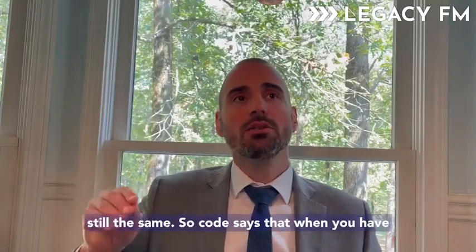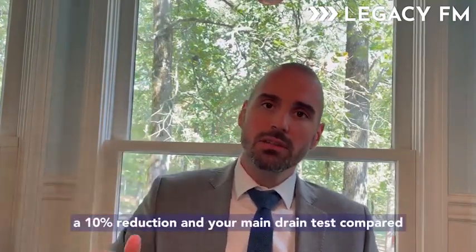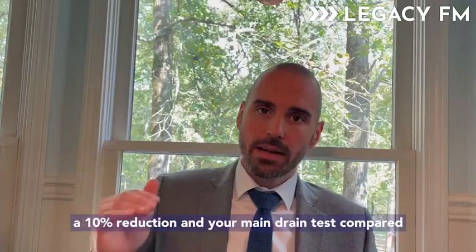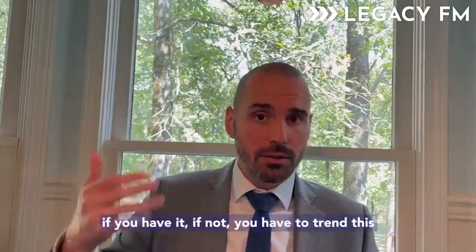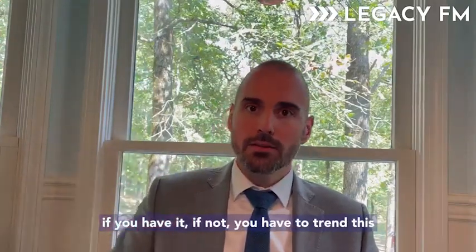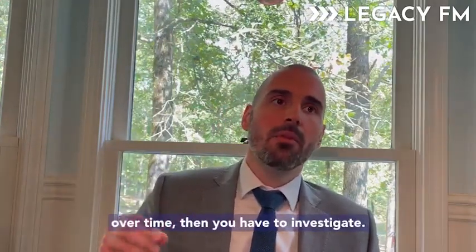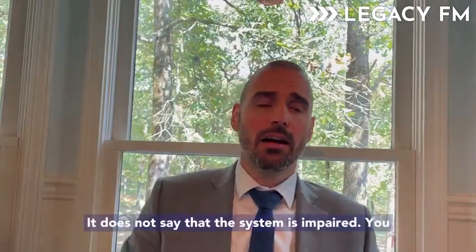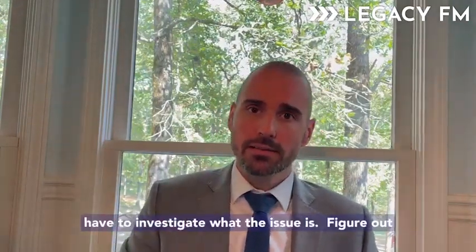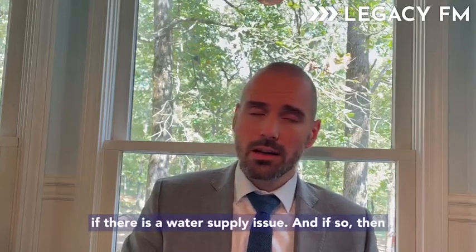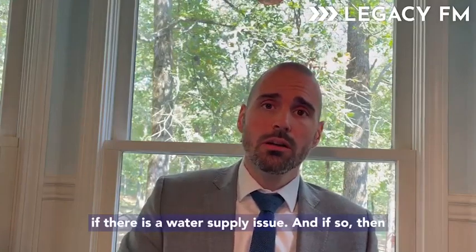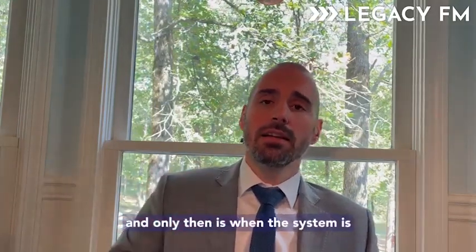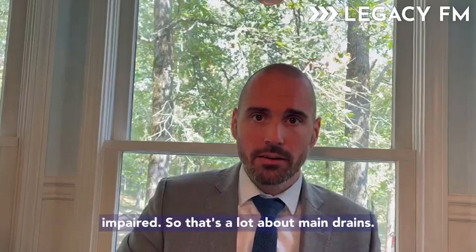So code says that when you have a 10% reduction in your main drain test compared to your previous results, preferably the original if you have it, if not, you have to trend this over time, then you have to investigate. It does not say that the system is impaired. You have to investigate what the issue is, figure out if there is a water supply issue. And if so, then and only then is when the system is impaired.